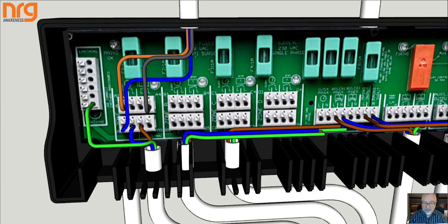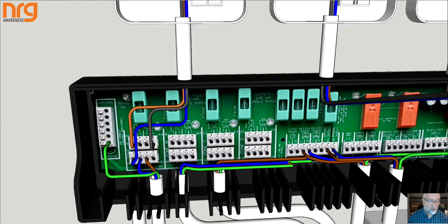So you can see here in the first scenario, we have live going off up to our OpenTherm controller through the brown wire from the 1 amp fuse. The switch live is coming down into the 4th, and the neutral is available in A5, and the neutral for the pump is A6. So now we'll move on to the OpenTherm.